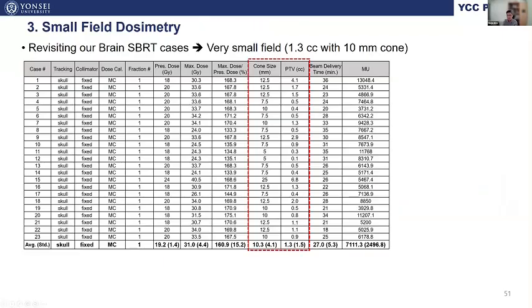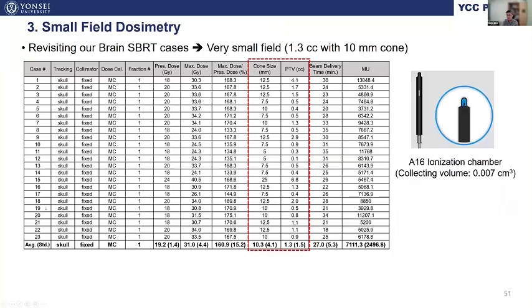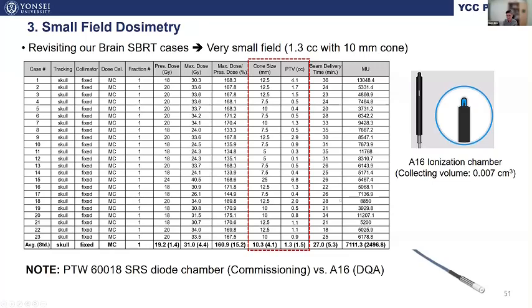The third issue is concerning the small field dosimetry. As mentioned earlier, our institution has been treating the brain SRS plans with very small field. To address this, we chose a A16 ion chamber for patient-specific QA having a collecting volume that is only 1% of the Farmer type ion chamber, which is very small, but volume averaging effect may not be fully overcome even with this type of chamber. Additionally, this ion chamber is not identical to the detector used for the beam commissioning process in our institution, which was SRS diode chamber. So this may require additional corrections for measurements.